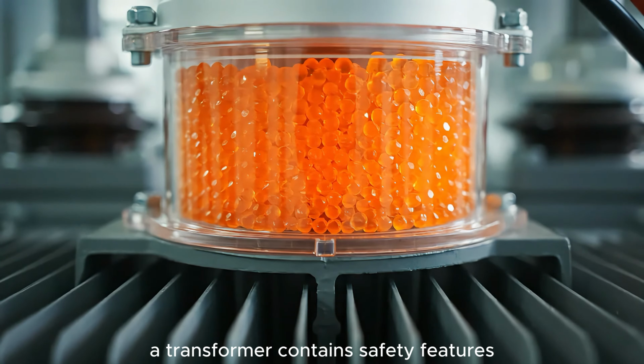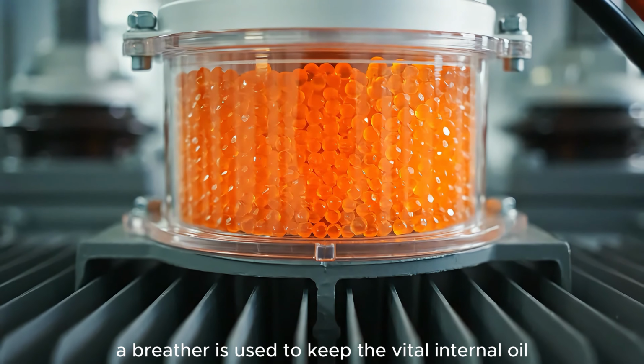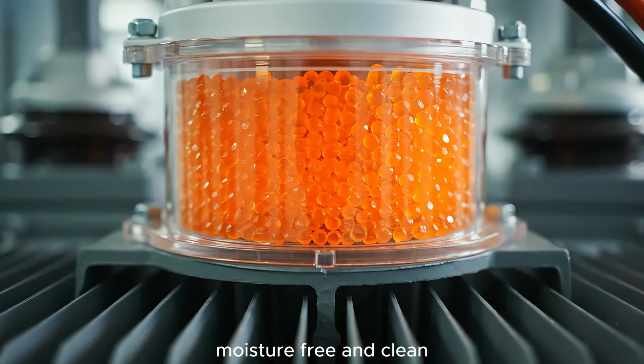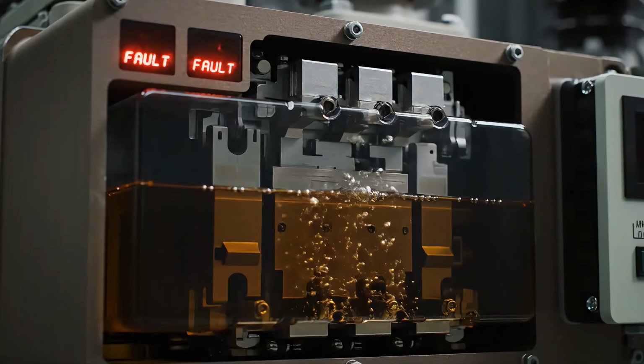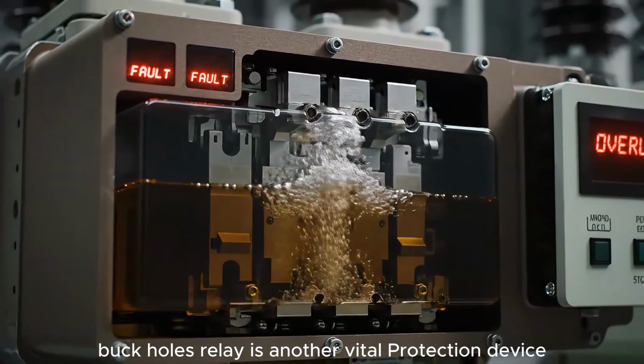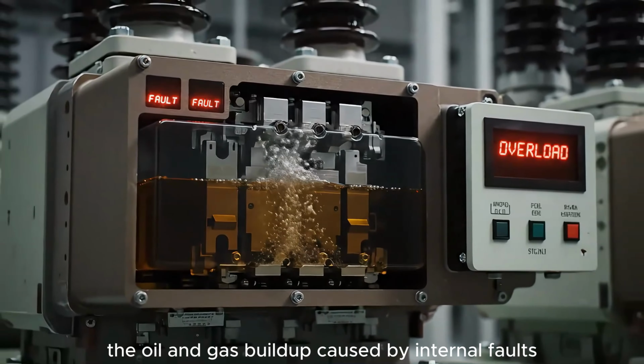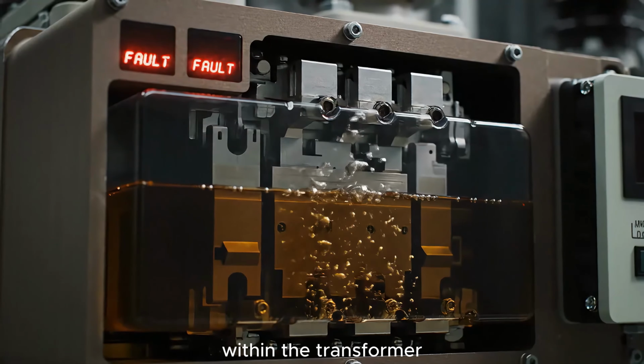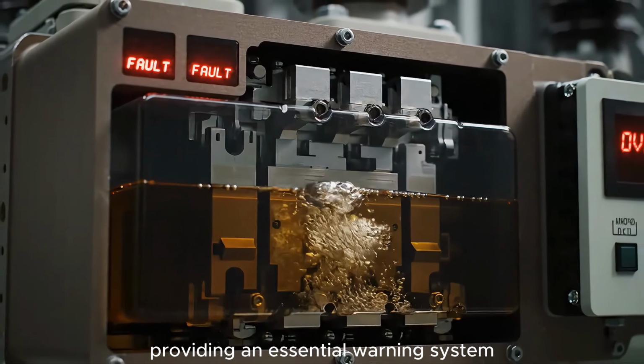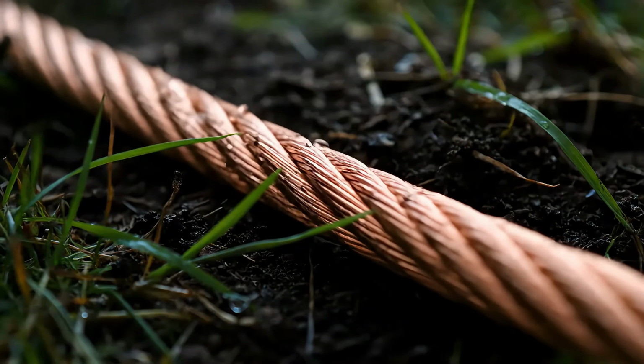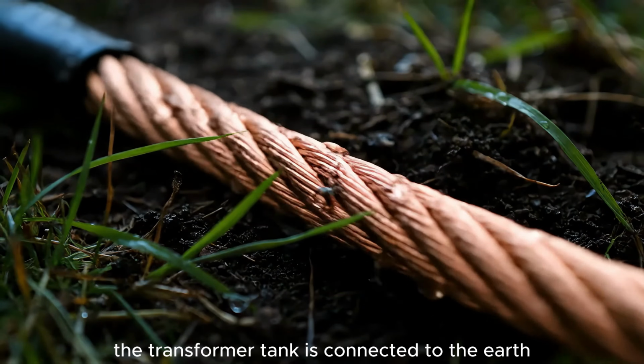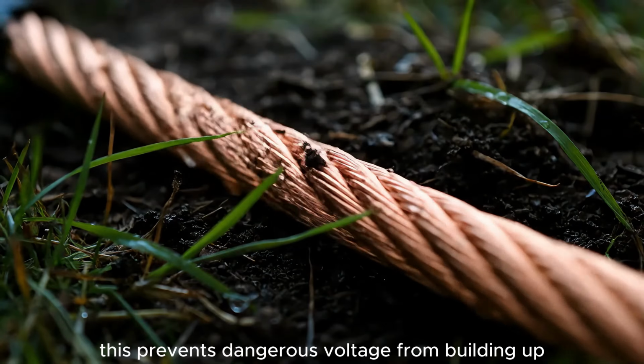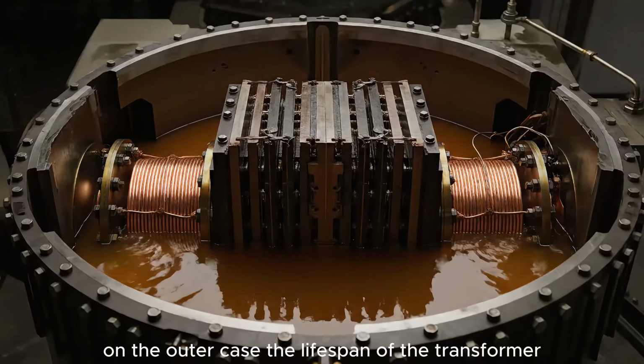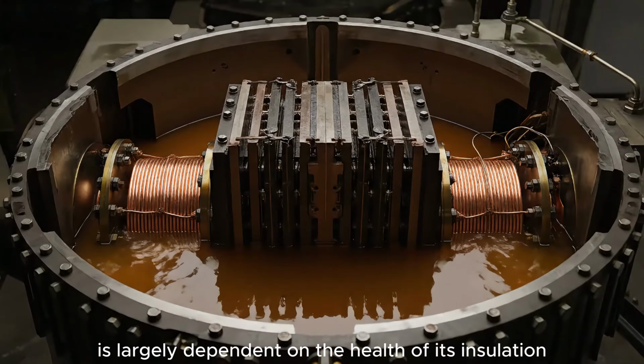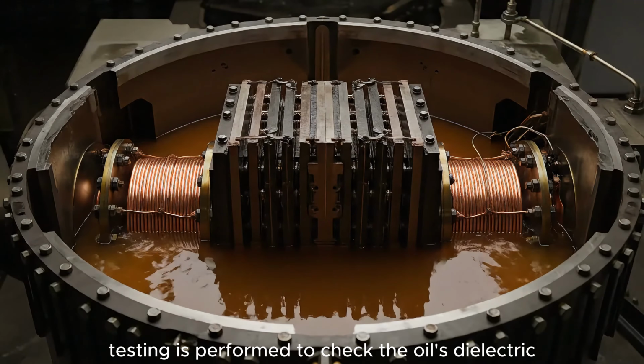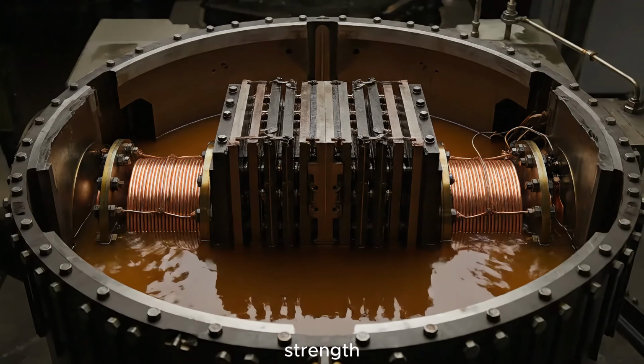Beyond the main windings, a transformer contains safety features. A breather is used to keep the vital internal oil moisture-free and clean. Buchholz relay is another vital protection device. It monitors the oil and gas buildup caused by internal faults within the transformer, providing an essential warning system. Safety and grounding: the transformer tank is connected to the earth. This prevents dangerous voltage from building up on the outer casing. The lifespan of the transformer is largely dependent on the health of its insulation and oil. Regular testing is performed to check the oil's dielectric strength.